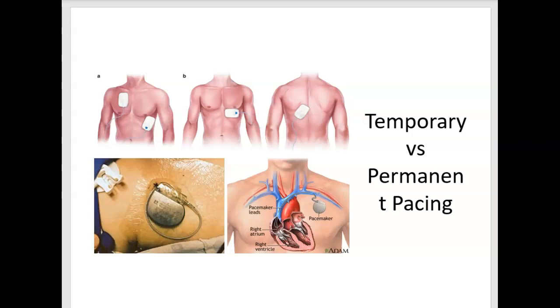A temporary transvenous system can be inserted in an emergency as a bridge until a permanent pacemaker can be inserted. It consists of an external battery-operated pulse generator and pacing electrodes or lead wire. The wire attaches to the generator on one end and is threaded into the right ventricle via the subclavian or femoral vein. The two major modes of pacing are synchronous or demand pacing and asynchronous or fixed rate pacing. Temporary pacing is usually done in the synchronous or demand pacing mode. The pacemaker's sensitivity is set to sense the patient's own heartbeats. When the patient's heart rate is above the set rate of the pulse generator, the pacemaker does not fire. When the heart rate is less than the generator setting, the pacemaker provides electrical impulses.